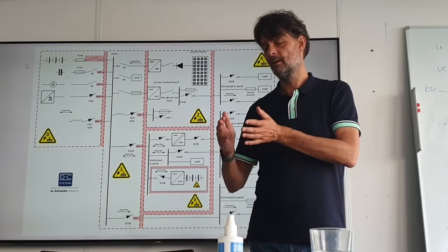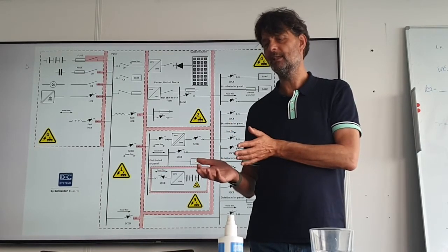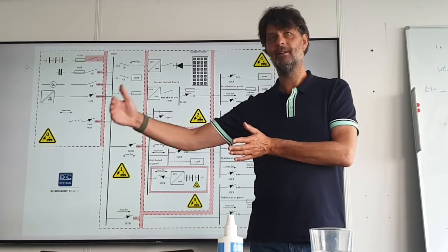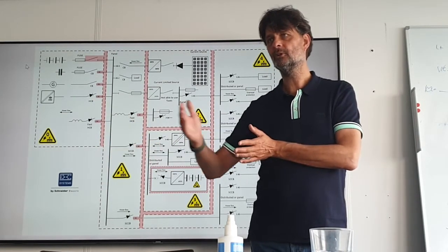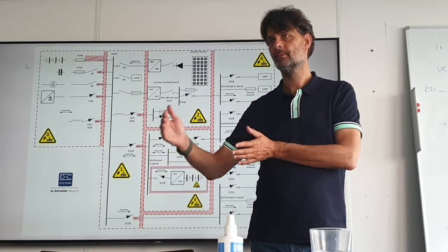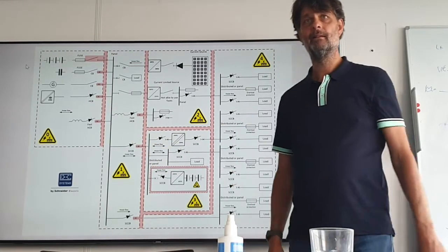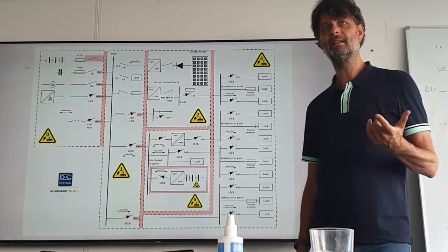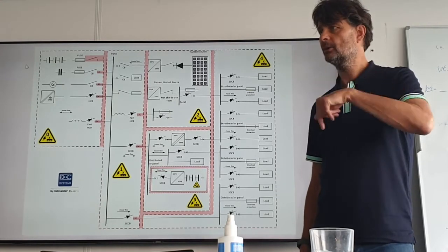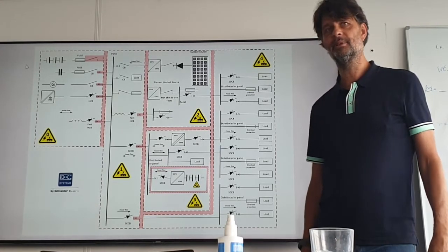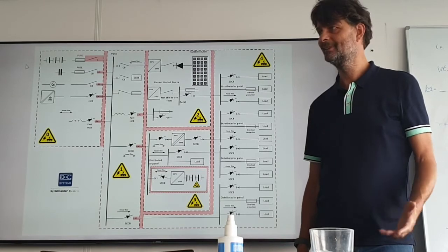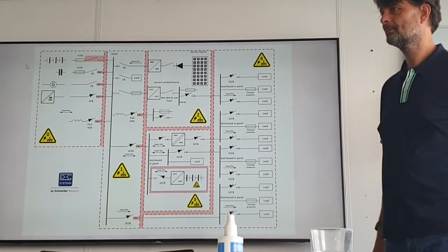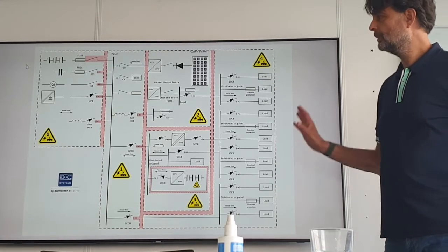So for us, the answer to the municipality was no, DC is not as safe as AC, DC is safer. Because it fulfills all the protective measurements which were not feasible with AC. Well, not feasible with an electromechanical protection system. But also the RCDs are not feasible, because if you have a 3.5 kilometer cable, you have so much current from capacitance that you cannot detect anymore. Yeah, but if you start to split earth and so on, you will also probably solve the capacitance issue. But that is the point.